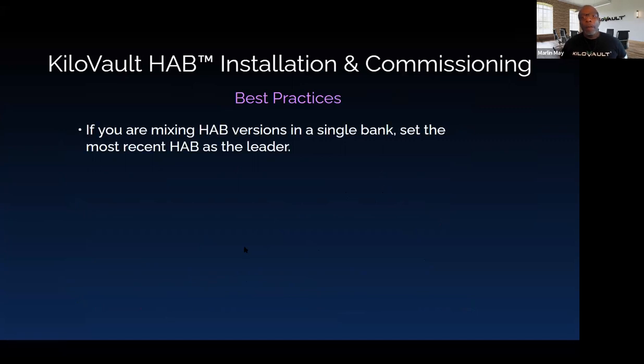Regarding adding new HABs to an existing bank — if you are mixing HAB versions, say adding a version four to existing version twos or threes, you want to set the most recent HABs as the leader. Things will work out better that way, and version four is much more adept at handling a mixed bank. If you do have version one HABs in your bank, please contact your distributor or KiloVault for assistance — we'll need to go over a few things regarding updating to make sure you don't run into issues.